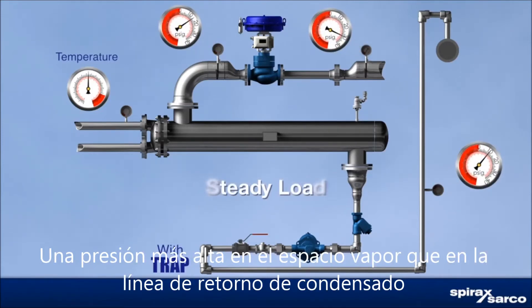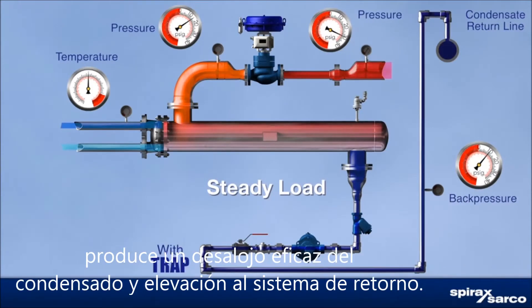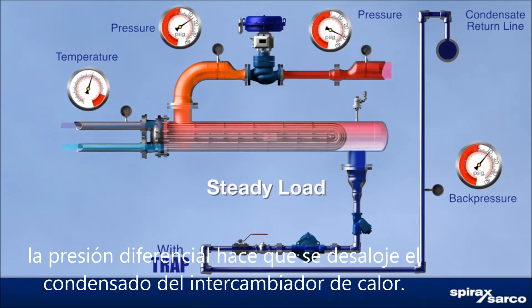Higher pressure in the steam space than in the condensate recovery line produces effective condensate removal and lift to the return system. Under a steady high load, differential pressure removes the condensate from the heat exchanger.